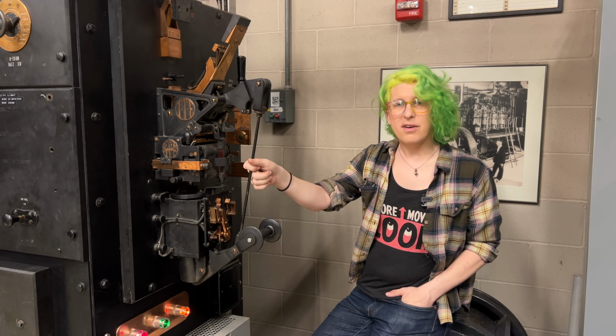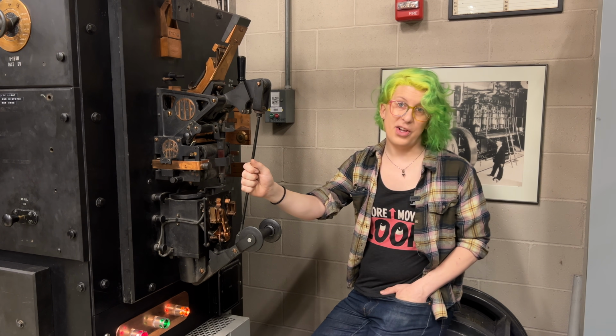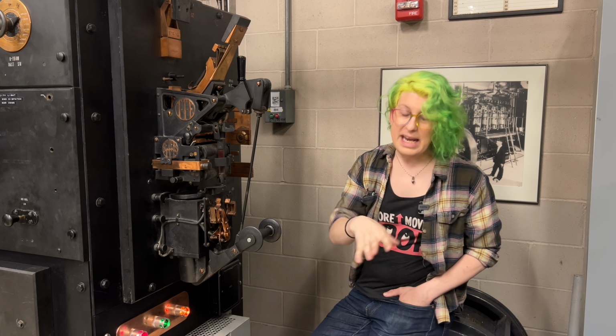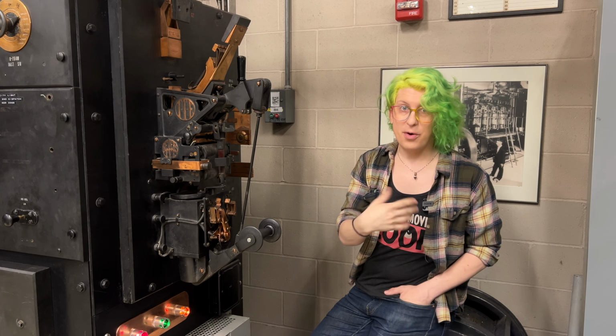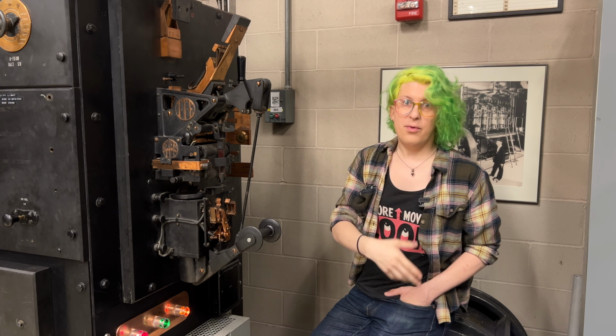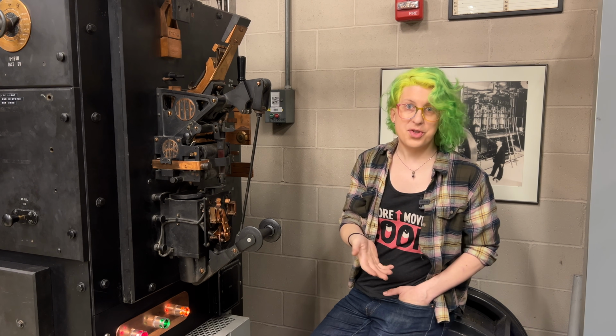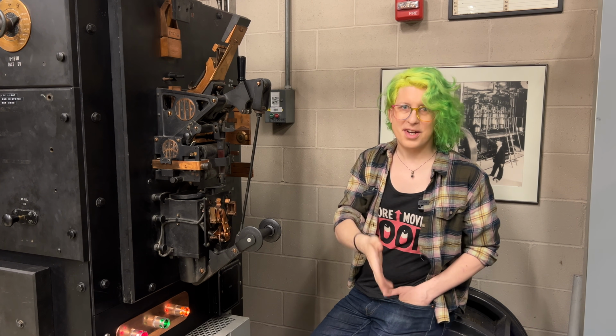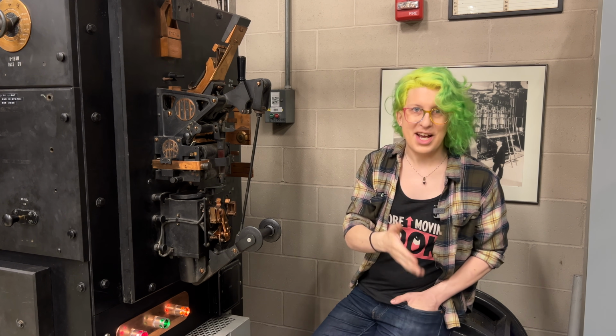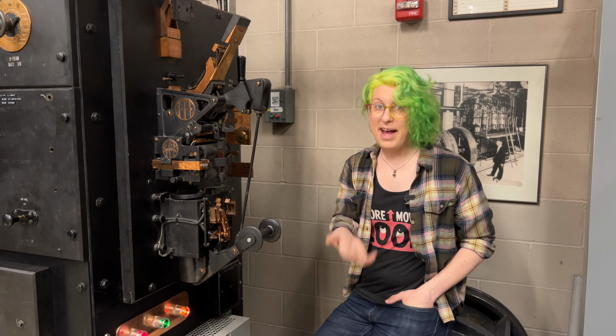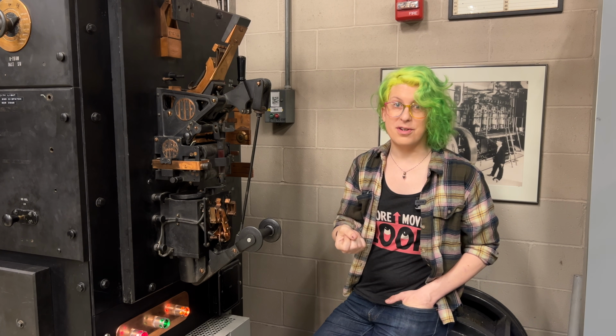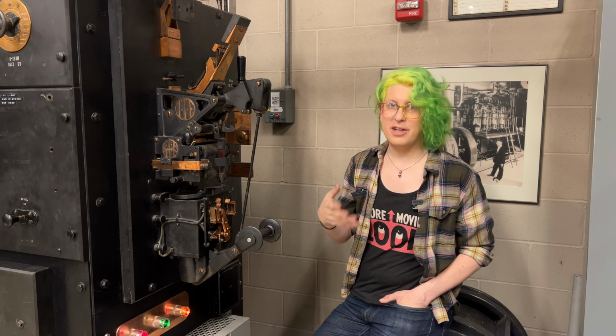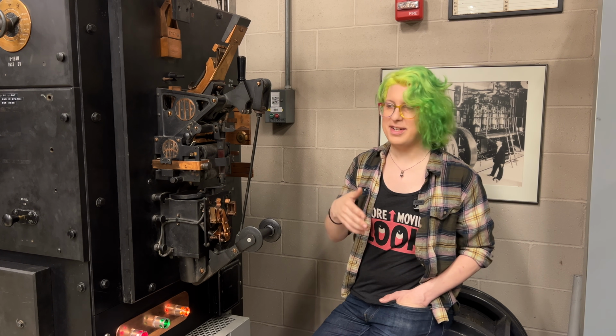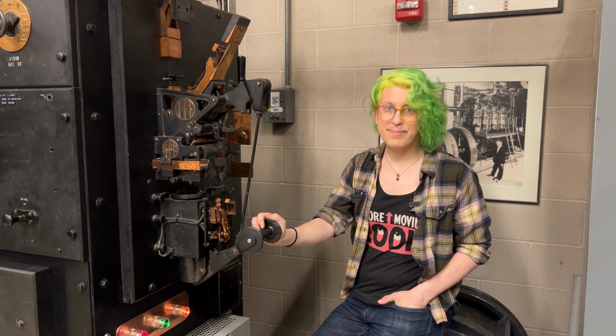This circuit breaker also provides protection against loss of power. If the main AC feed is lost, the motor generators would shut off. And when the AC power is eventually restored, we don't want to suddenly start all of the generators at once. That would put a heavy instantaneous load on the power service. And if this were, for example, a factory and the power went out, you wouldn't want power being delivered to all of the machinery in a sudden, uncontrollable way.